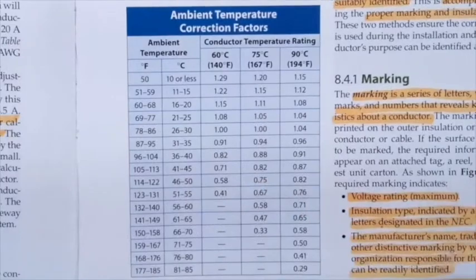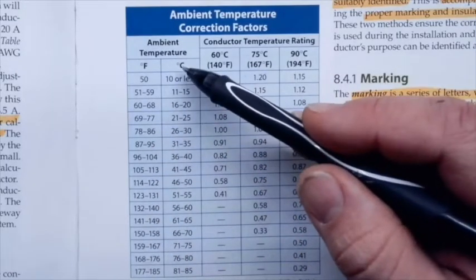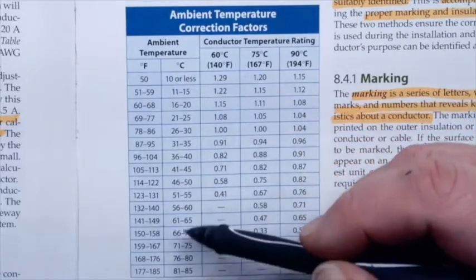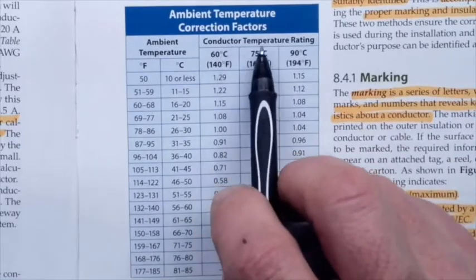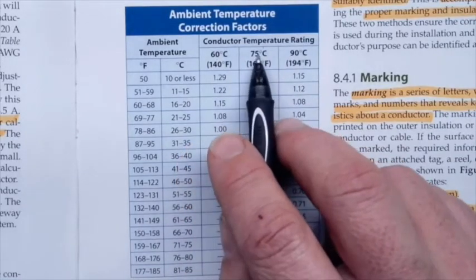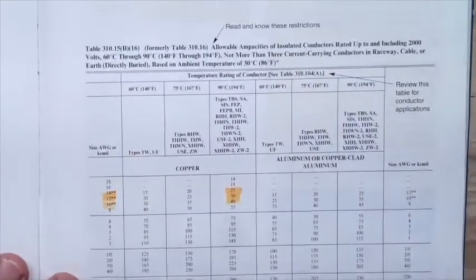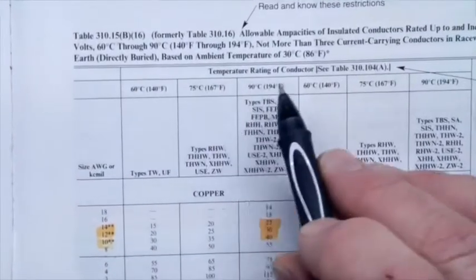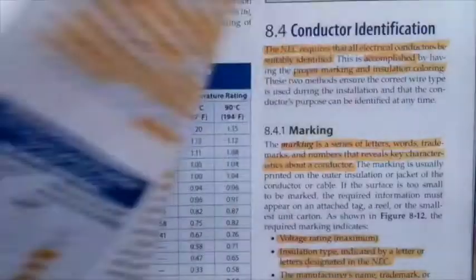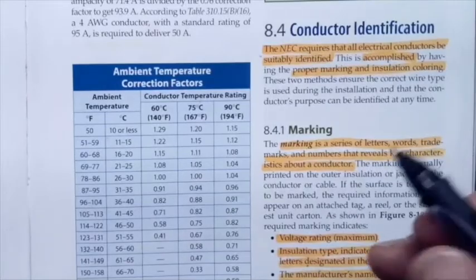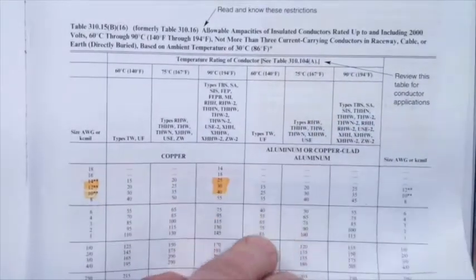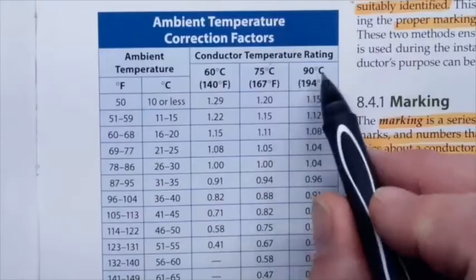If we go to our chart, it says ambient temperature correction factors. The first thing to notice is that we have Fahrenheit here — that's what we'll use most of the time — but sometimes a question may be in Celsius, so know where to find that. From there we have conductor temperature ratings: 60°C, 75°C, and 90°C. If we cross-reference back to the ampacity table, we see those same three columns. For example, THHN is in the 90-degree column, so when I need a temperature rating for THHN, I use the 90°C column.